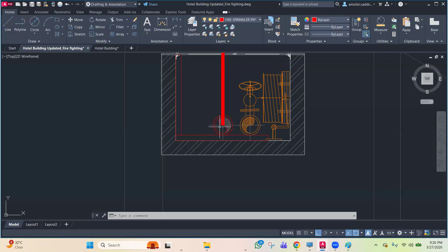So mostly the vertical riser that you see over here is connected at the basement level to the fire pump discharge line - there is a fire pump discharge line. So this pump draws water from the fire tank and supplies it under pressure to all floors through the riser. At each floor, a landing valve is connected inside the hose cabinet for firefighting uses. So the important thing to note over here is that a riser is always pressurized and it runs continuously from bottom to top.